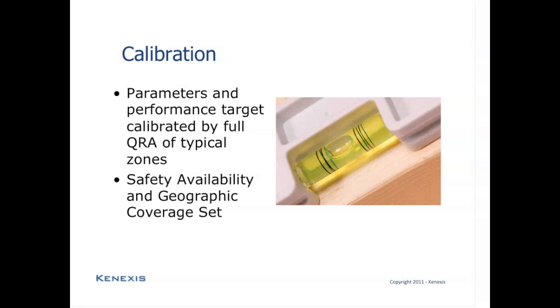It's also important to note that the calibration technique is typically going to be based on geographic coverage as opposed to scenario coverage, because what has been determined by experts in the field through numerous full QRA calibrations is that geographic coverage for a well-defined zone is going to correlate very well to scenario coverage, which then correlates very well to overall risk. And since calculation of geographic coverage is significantly easier to perform than scenario coverage, most organizations' performance-based fire and gas philosophies dictate the use of geographic coverage as opposed to full scenario coverage.